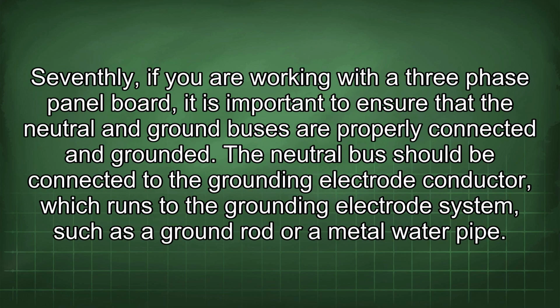Seventhly, if you are working with a three-phase panel board, it is important to ensure that the neutral and ground buses are properly connected and grounded. The neutral bus should be connected to the grounding electrode conductor, which runs to the grounding electrode system, such as a ground rod or a metal water pipe.